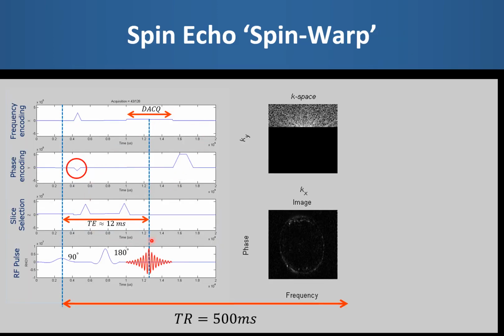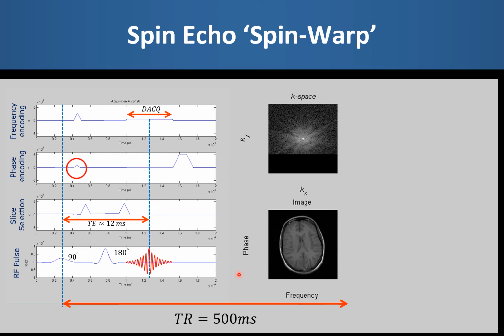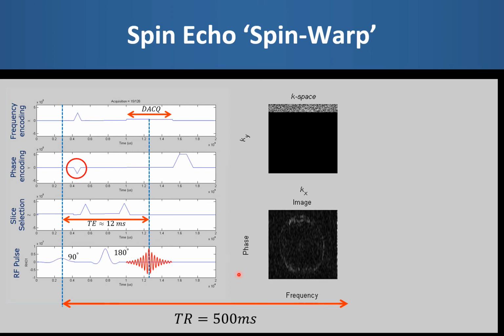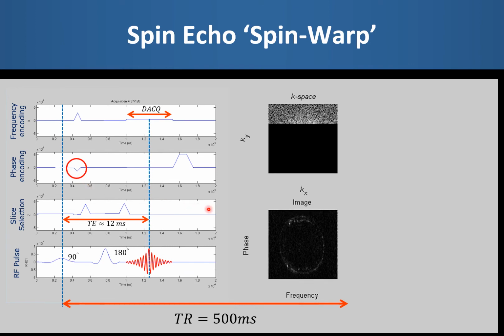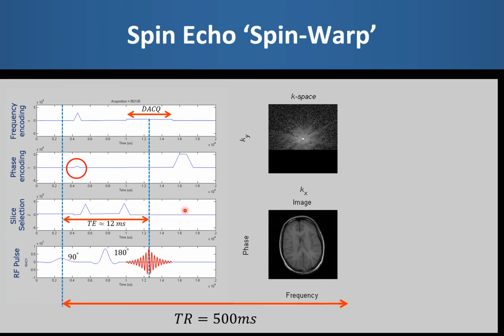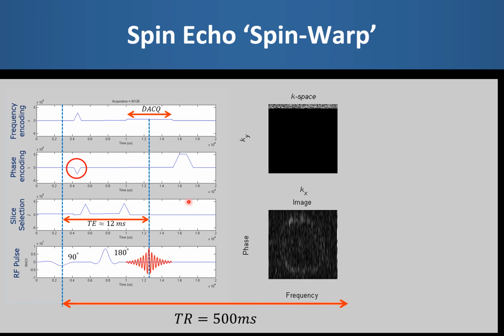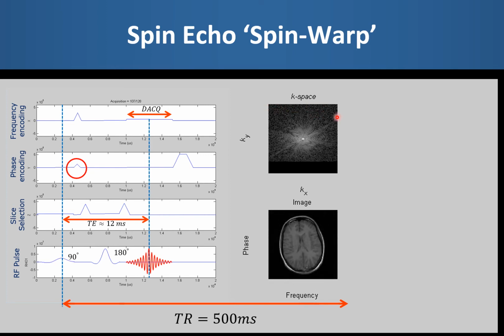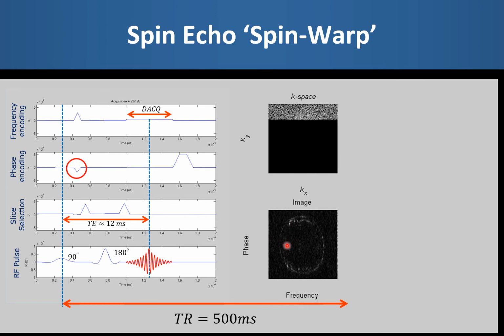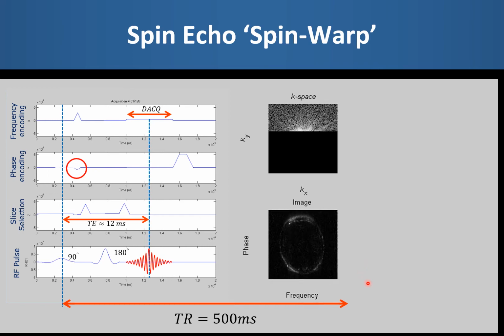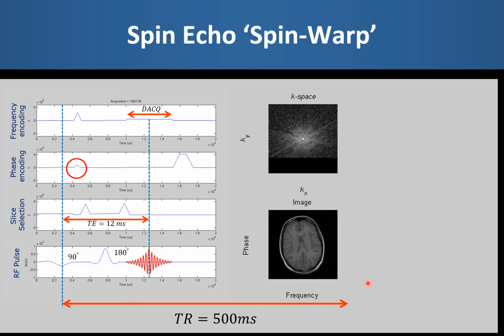This movie shows a real spin echo pulse sequence with 128 phase encoding steps acquired on one of our clinical MRI systems. Note that all the gradients are the same except for the phase encoding gradient, circled, that is stepped plus or minus 64 times from a maximum negative area through to a maximum positive area. Each echo is then placed in the appropriate point in K-space, and in this example I have performed a Fourier transform of the partially filled K-space as each KY line is acquired. Note that in clinical MRI systems the image is not reconstructed until all of K-space is filled.